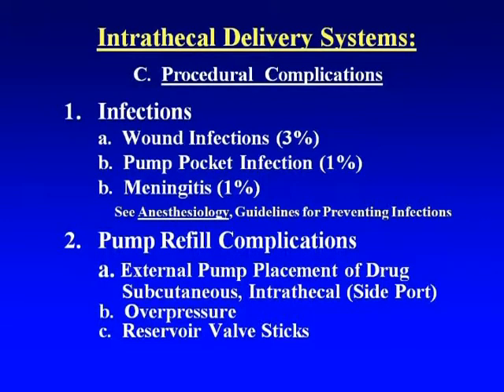But pump refill errors are common and still occur. Overpressure doesn't occur that much because of the check valves that are in place, but you can still overpressure a system if you refill the reservoir too quickly, and the pressure is transmitted to the tubing, and the drug can be forced around the rotor and be injected into the neuraxis. The reservoir valves can stick, although they're pretty good now. With the new pumps, I haven't heard of much in the way of problems with that.